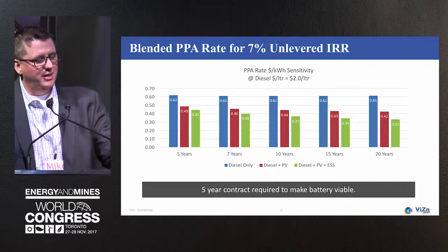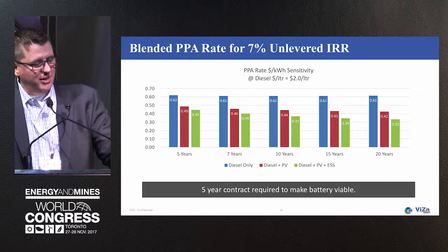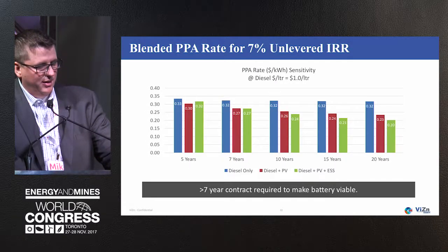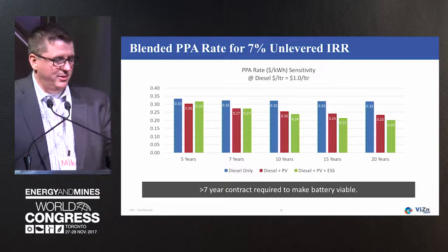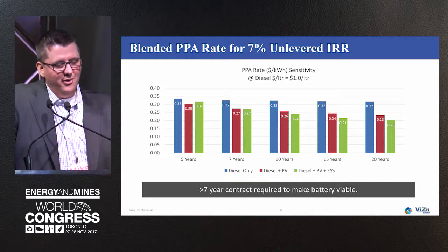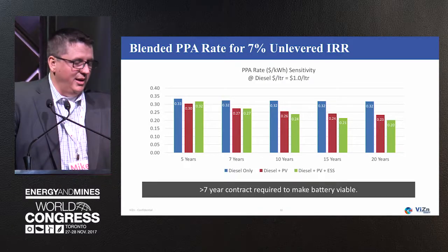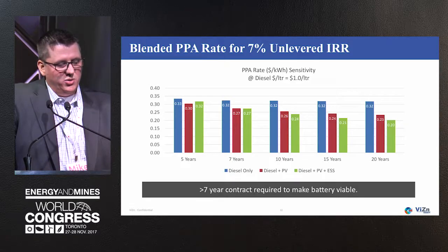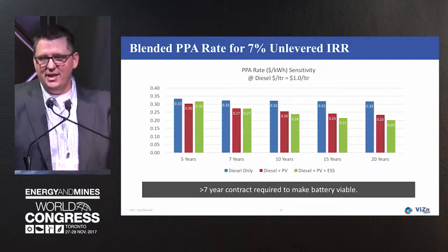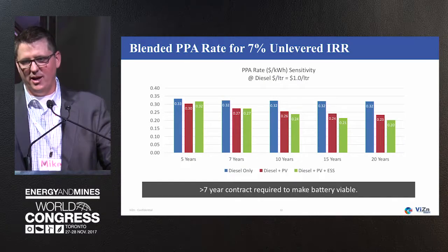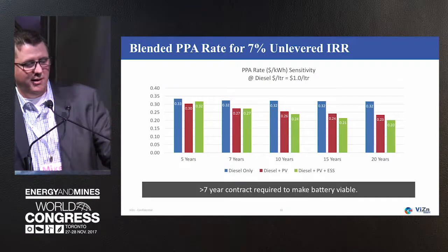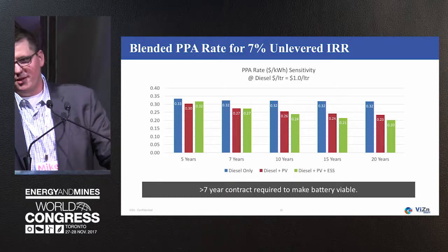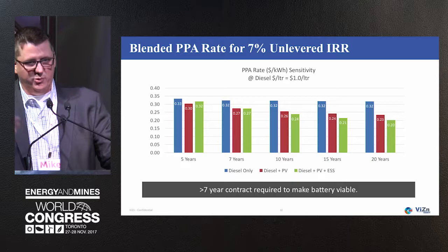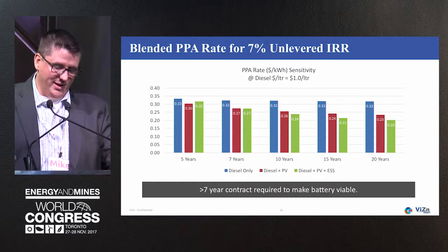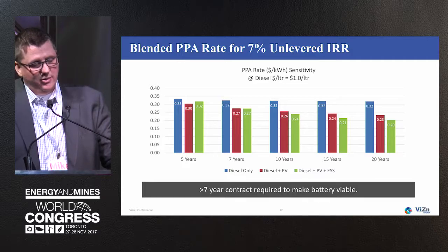However, when you go to the higher diesel scenario, it's interesting. Even at 7 years in the low diesel cost scenario, the solar alone and the solar plus storage are at 27 cents a kilowatt hour. So it's an equal payment, equal price per kilowatt hour. Both of those are about a 20 to 23% reduction in your overall annual spend on energy and your overall annual spend or annual emissions targets, which is interesting.